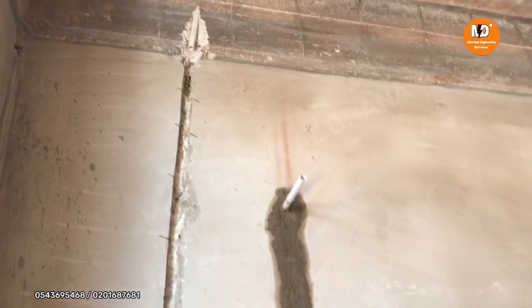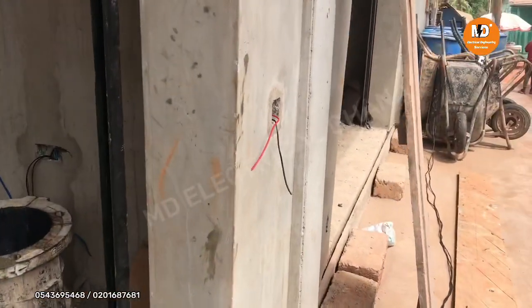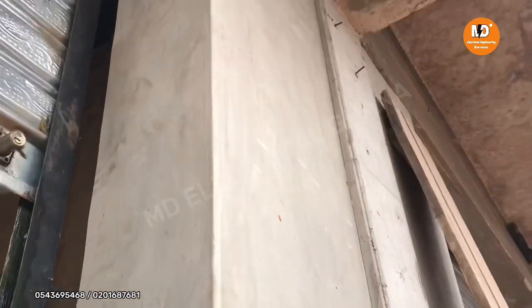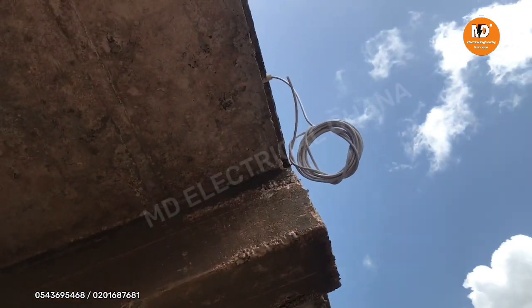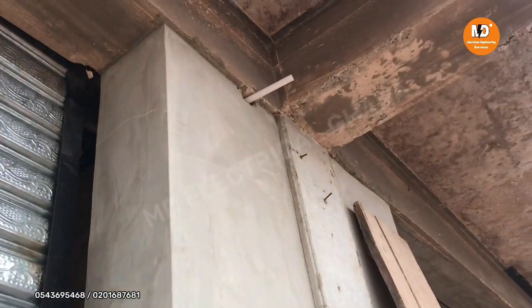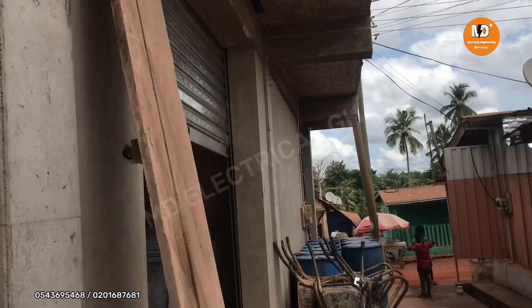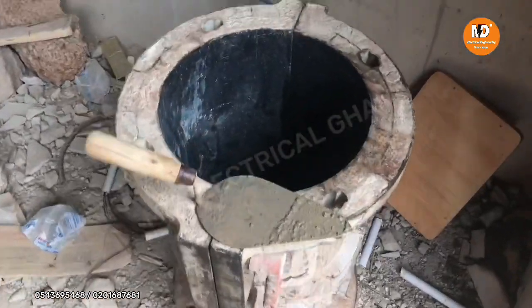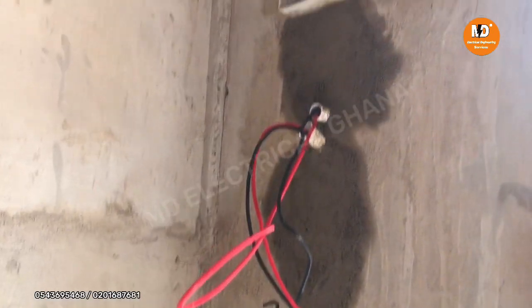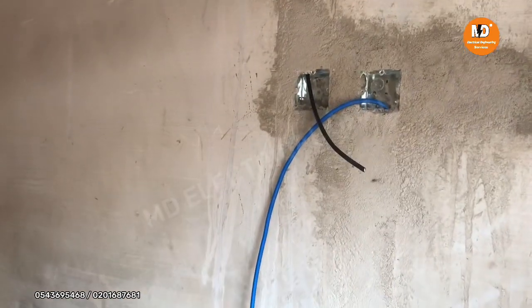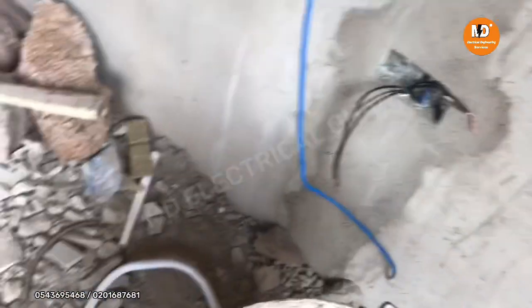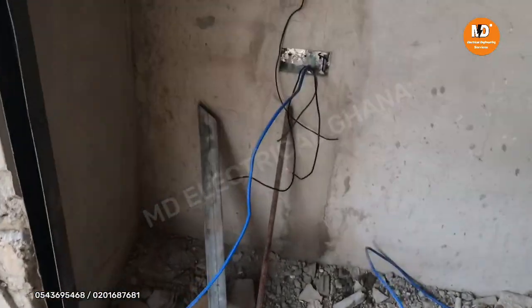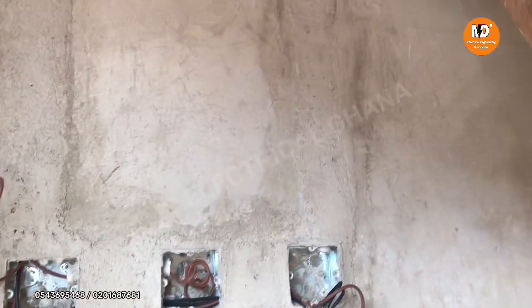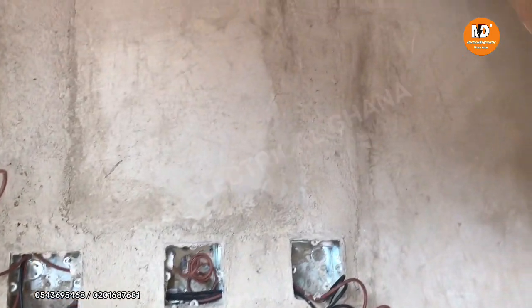Okay, so this is day two of our electrical installation work, or wiring. So what you are seeing there is a coaxial cable for our satellite installation work. That PVC pipe is what we will use to transmit power from the ECG power point to the distribution board. So that's the end of the coaxial cable for our satellite installation work. Here a 3x3 13 amp twin socket will be installed, a switch, a fan, and then an AC system will be installed right here. And that's our ceiling.